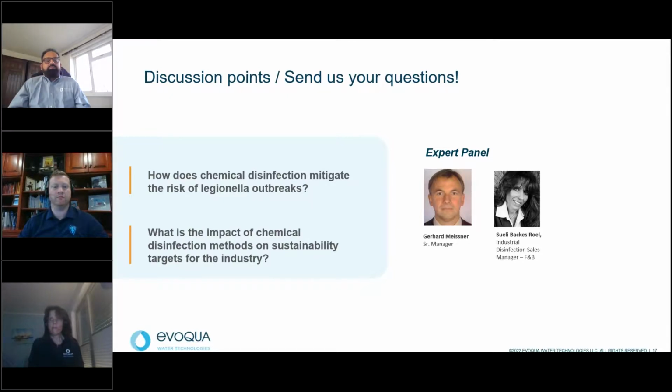An additional effect that is worth mentioning in this context is the decay of commercial hypo that needs to be considered, which means that 20% of the chlorine decays within a month roundabout. And this is a striking advantage also of our OSEC technologies, because we produce just a solution that is required for the immediate consumption.